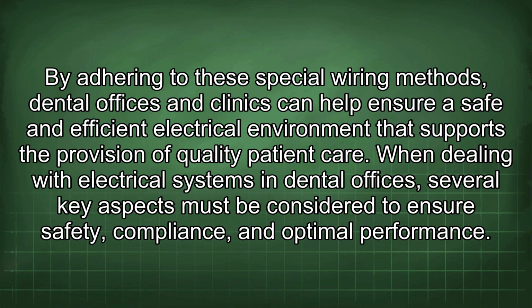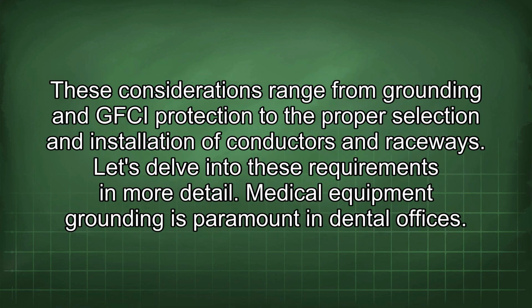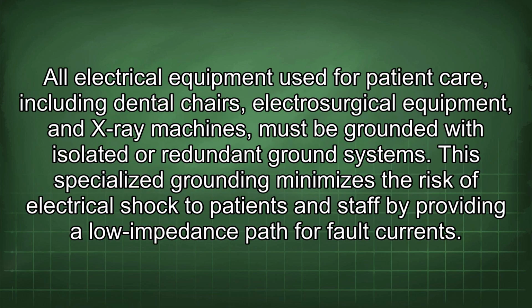When dealing with electrical systems in dental offices, several key aspects must be considered to ensure safety, compliance, and optimal performance. These considerations range from grounding and GFCI protection to the proper selection and installation of conductors and raceways. Let's delve into these requirements in more detail. Medical equipment grounding is paramount in dental offices. All electrical equipment used for patient care, including dental chairs, electrosurgical equipment, and X-ray machines, must be grounded with isolated or redundant ground systems. This specialized grounding minimizes the risk of electrical shock to patients and staff by providing a low impedance path for fault currents.